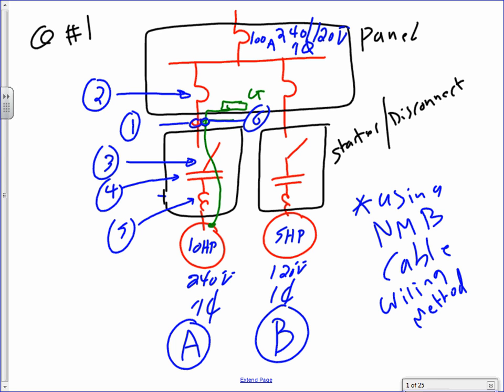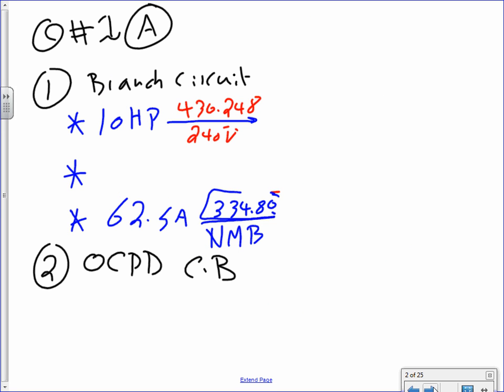So let's go size the equipment. The first thing you need to do, guys, for these motors, obviously, is to go find the full load current. Like we did yesterday, if you go to a 10 horsepower from 430.248 at 240, you're going to end up with 50 amp. You got yourself a 50 amp. That's just finding the full load current.